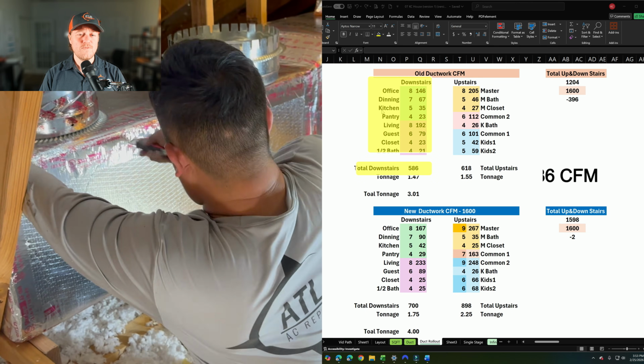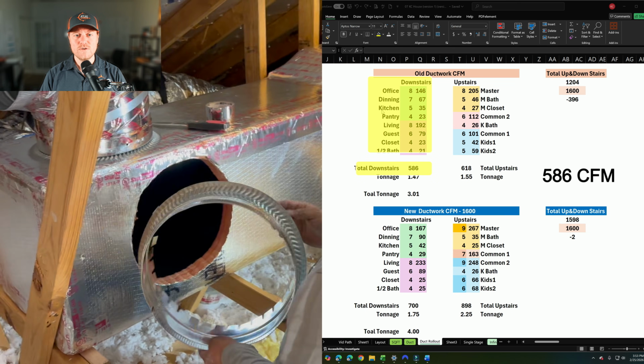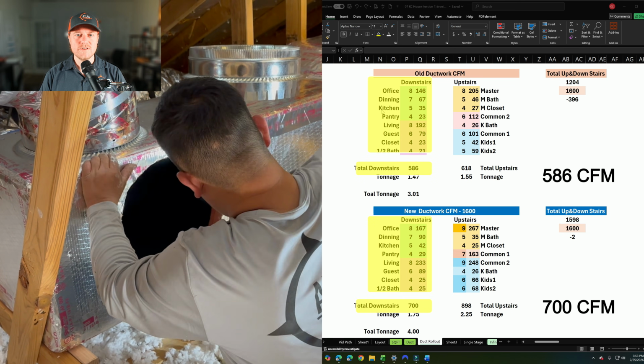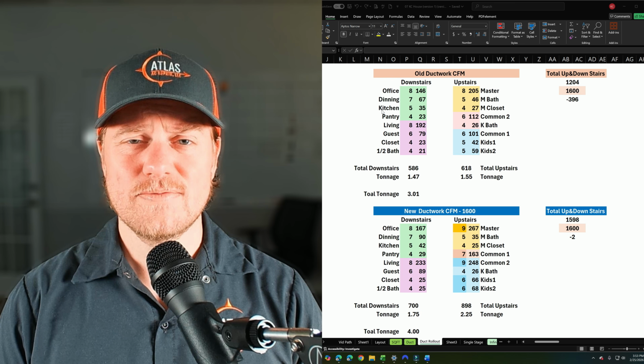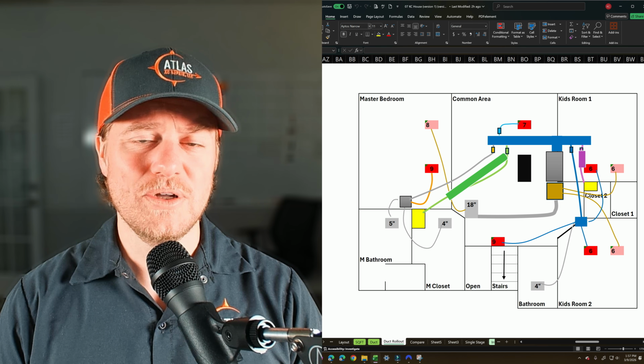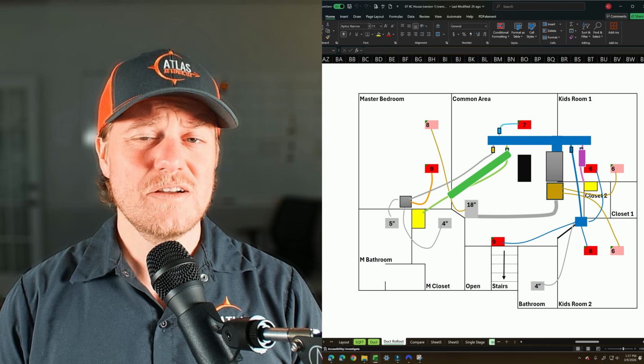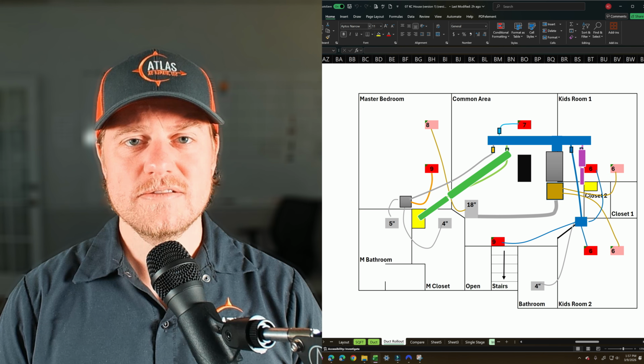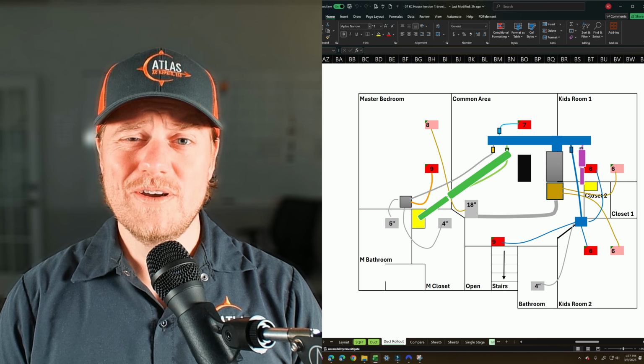It used to deliver 586 CFMs of airflow. Now we're looking at 700. By increasing the size of the ducts from a 10-inch to a 12-inch at the plenum, and tying that 12-inch duct back to the 10-inch before the chase, we were able to increase airflow fairly decently.